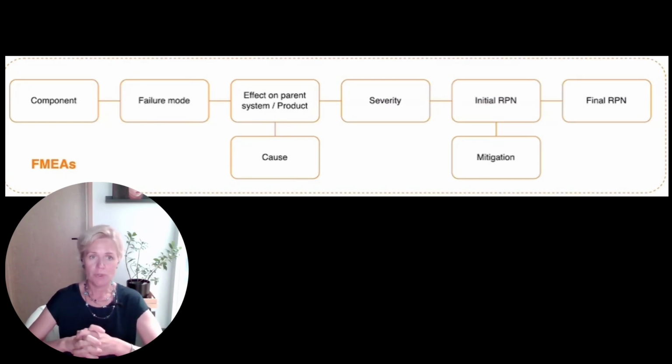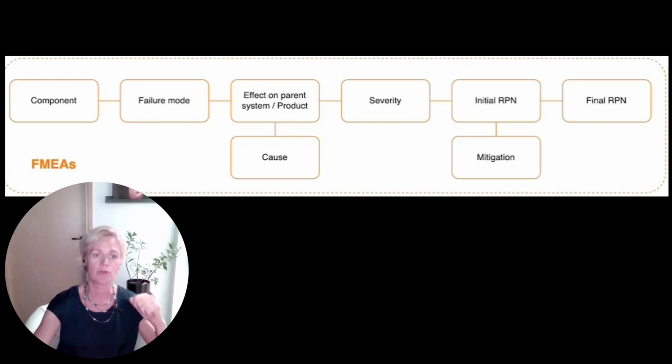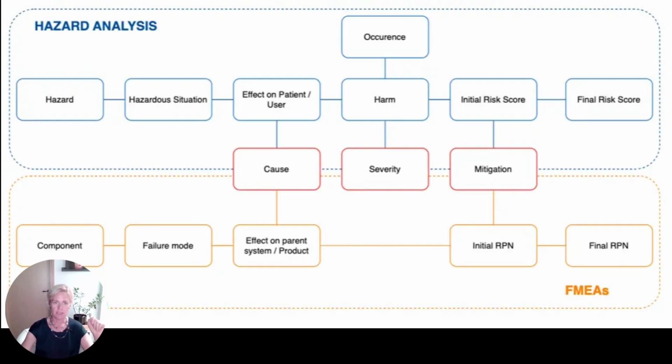And you should also report everything that you have documented. For the auditor, you need to have your risk management plan and risk management report in place, and FMEA reports are part of that. I mentioned that last week about hazard analysis, so let's also look into what is the difference between hazard analysis and FMEA.